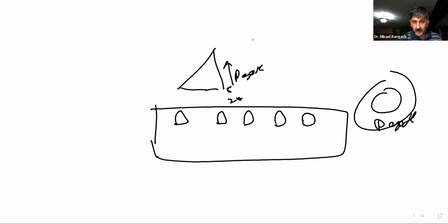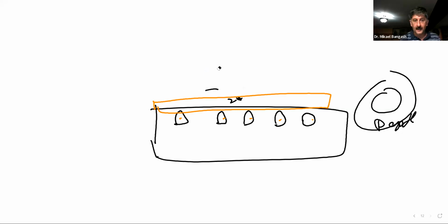But then, on your keyboard, we had these 5 knobs here. Right next to them was the screen, this touch screen. So there are some other functions and things like that on the screen as well. But right next to each knob, you will see different things written. Now that's first of all going to depend upon what mode is on. Now in your B mode, this one here was going to be your power output.